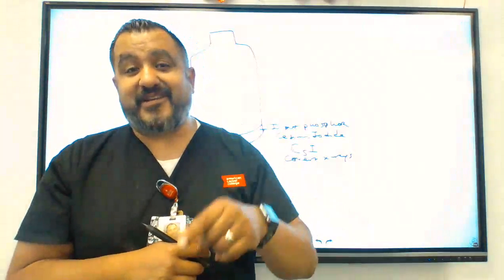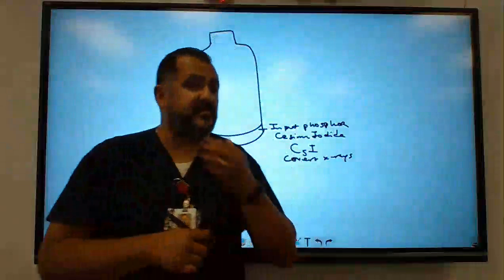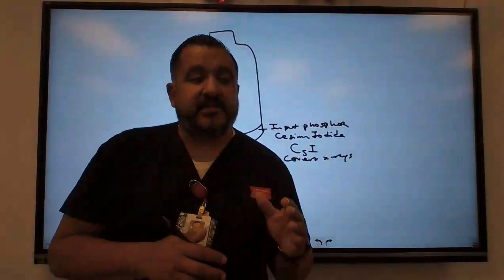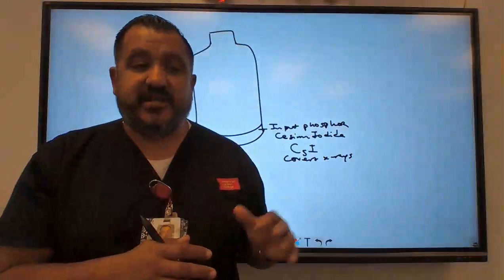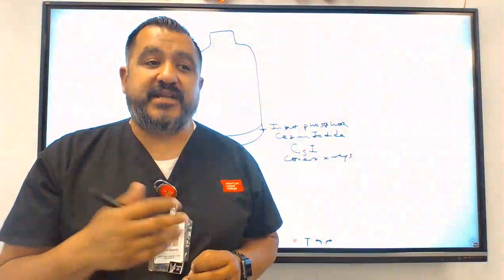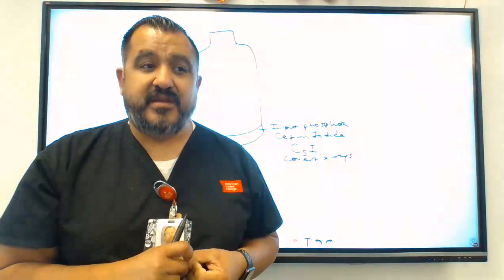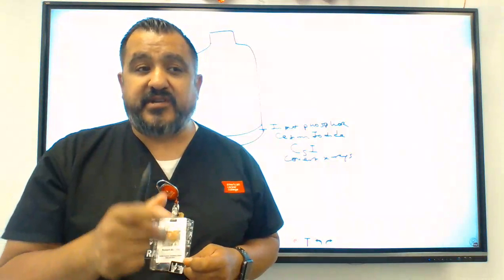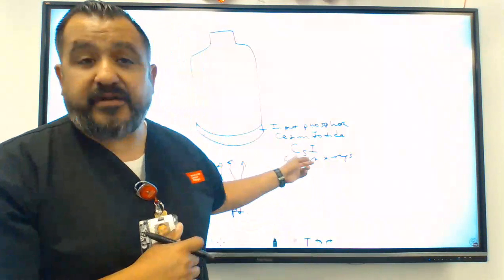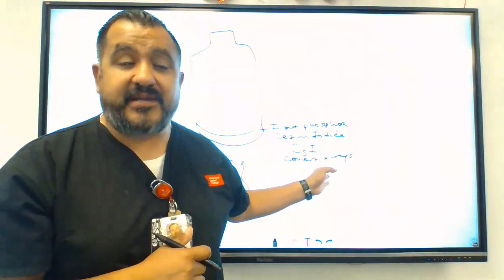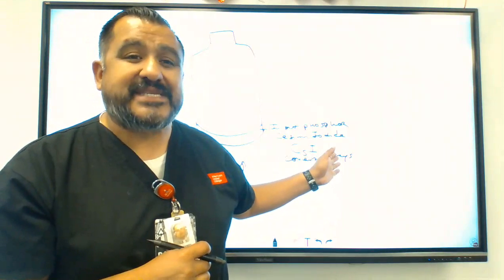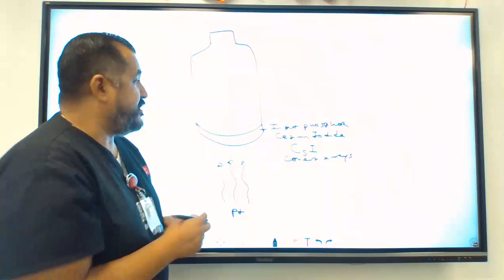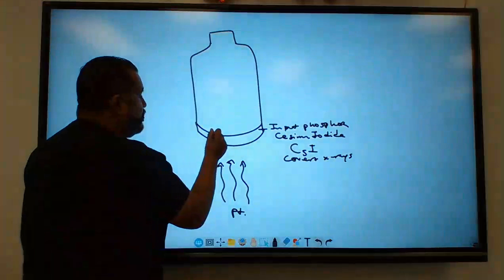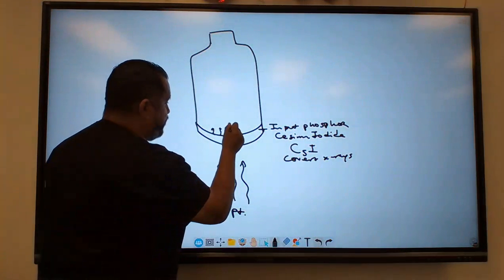We'll talk about it again today when I do a video on DR systems. X-rays hit the scintillator, it glows and produces light, then it hits amorphous silicon—do you remember that? That same material found in indirect capture DR systems is found here. Cesium iodide is probably the most common scintillation material used in radiography.